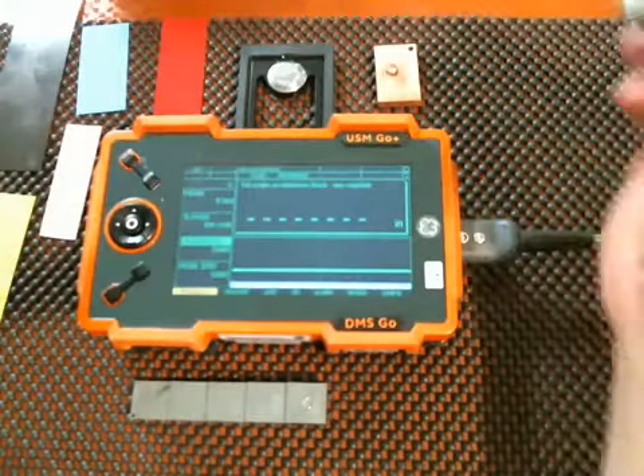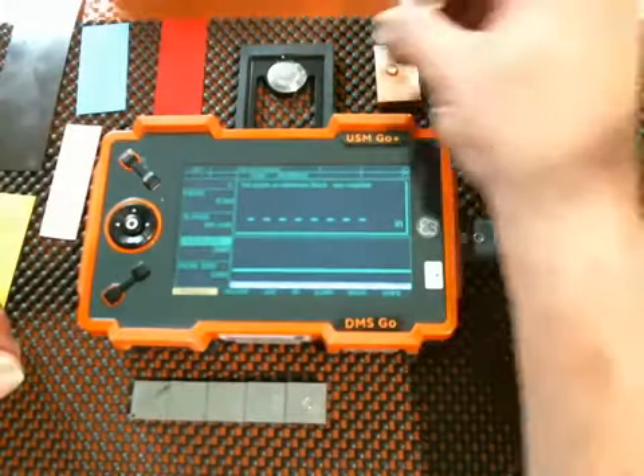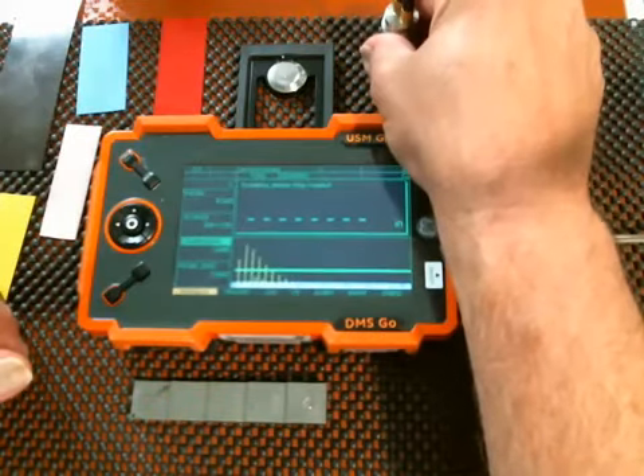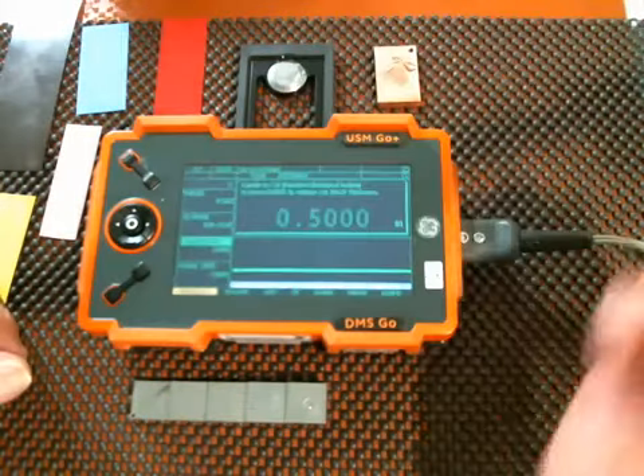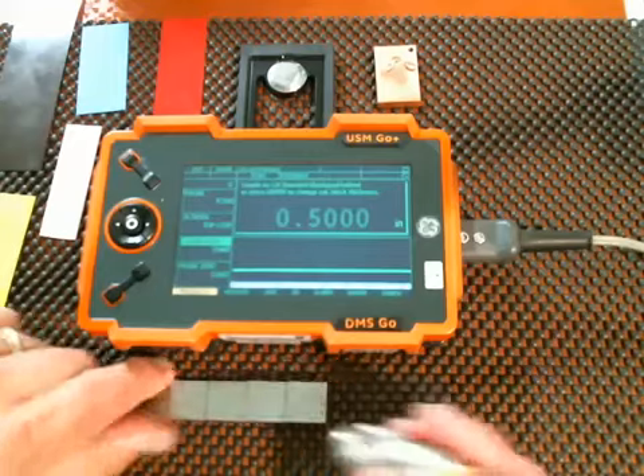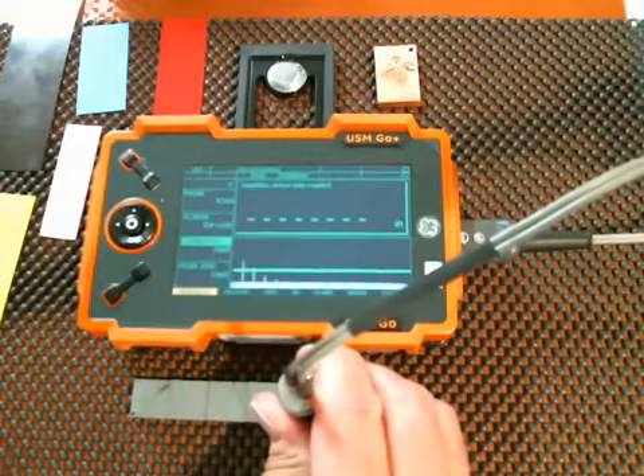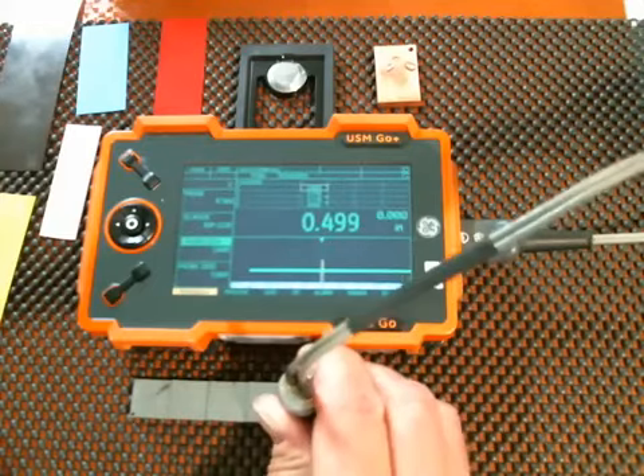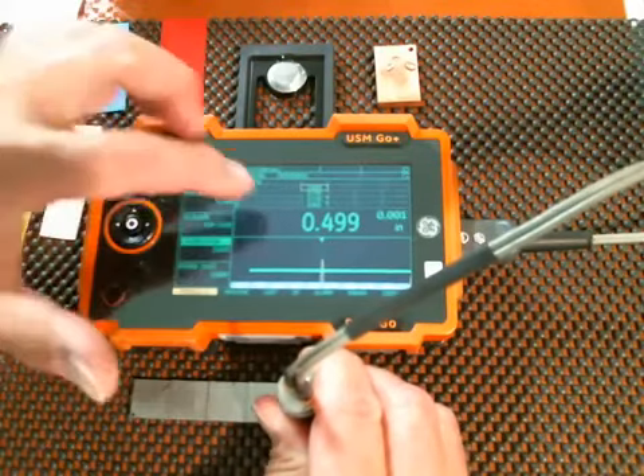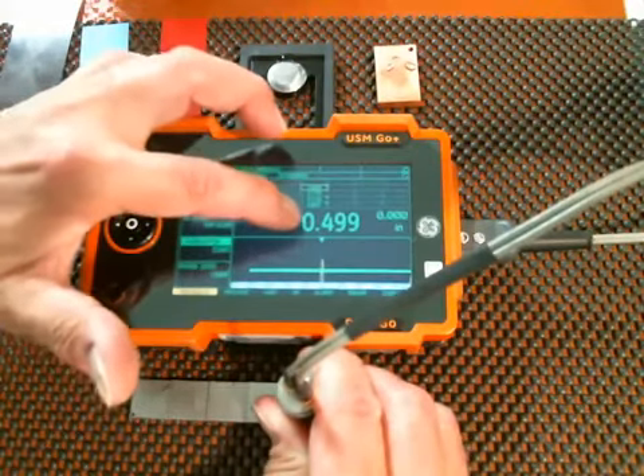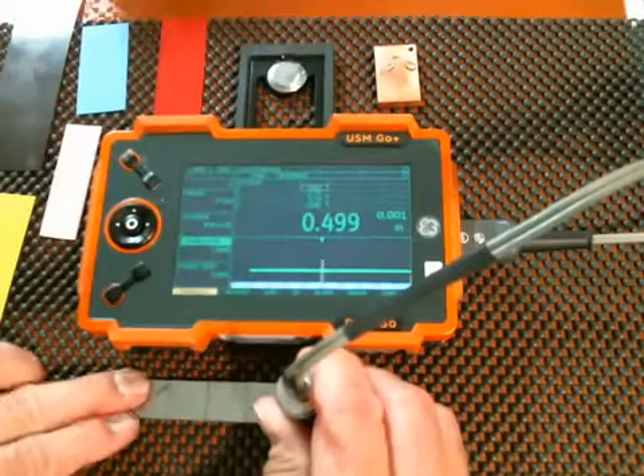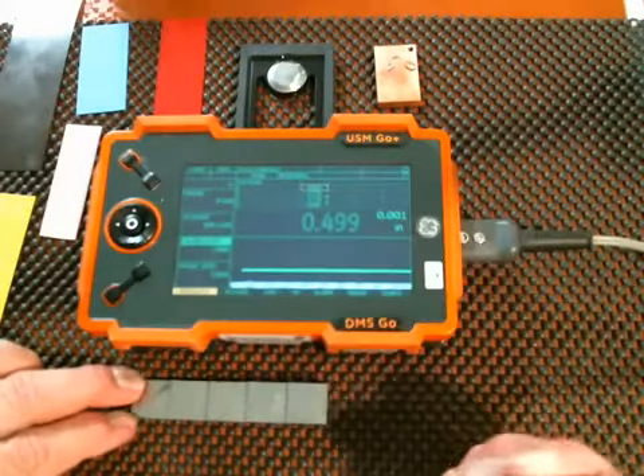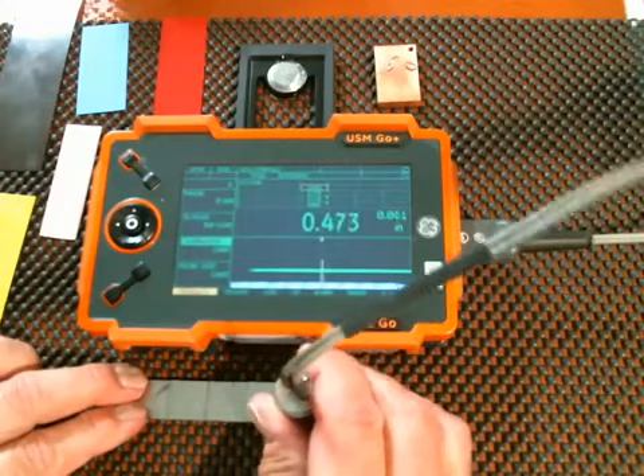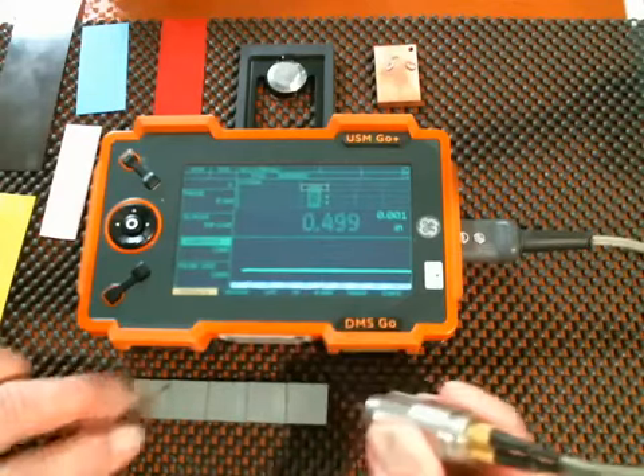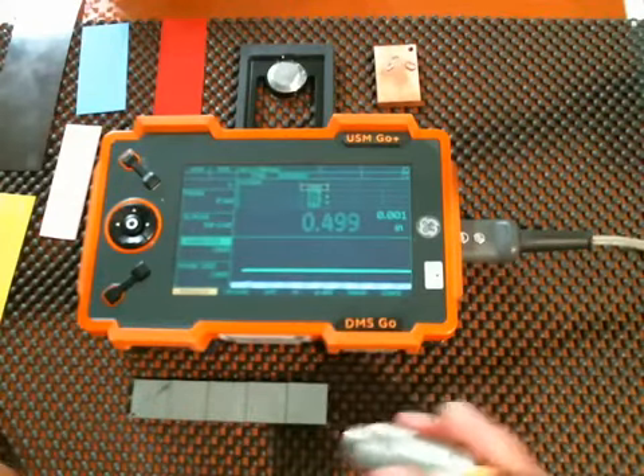Okay. Now it's time to go to the velocity reference block. That's the copper block. Couple up. Complete. Okay, now it says go to my standard calibration block. So I go to my 5-step block, go on the 1/2-inch, and I've completed the calibration. Now you'll notice my display is showing me both thickness and a coating thickness. The smaller number is the coating thickness, the big number is the material thickness. Now you may notice a little bit of variation in coating and thickness as we squeeze couplant out from between the block and the probe.